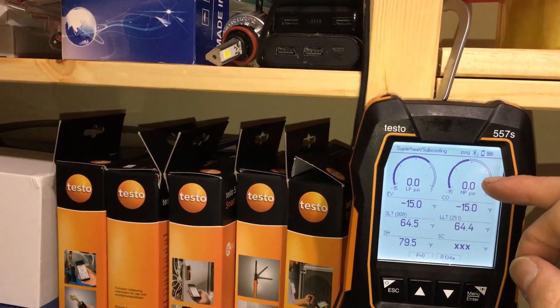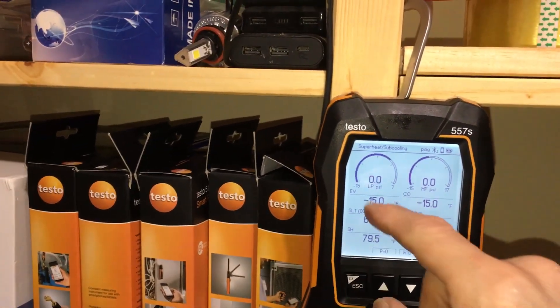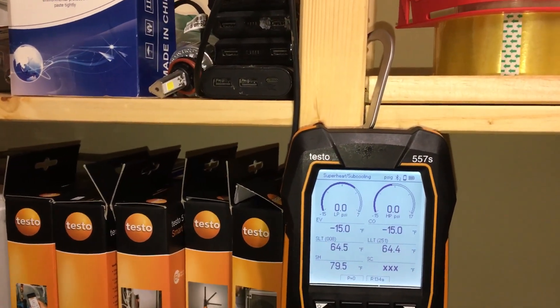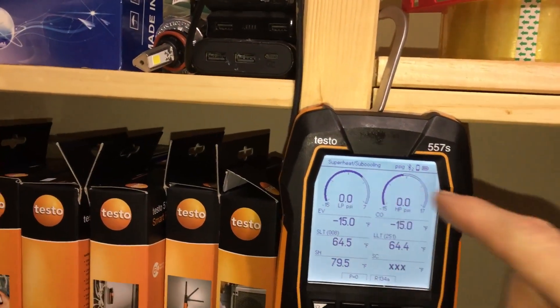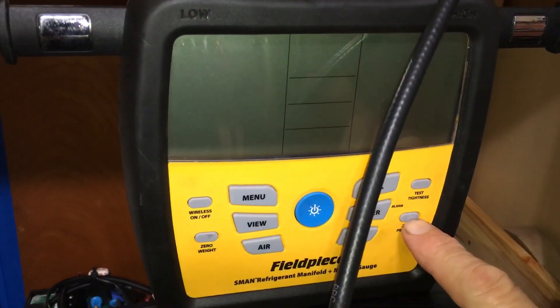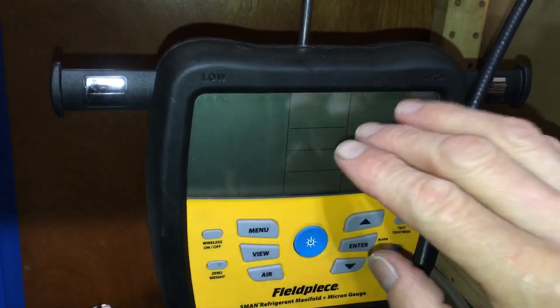So what we have here is I'm at 0-0 now, but that's not what I had. I had 8 PSI and I had like 1.5 PSI on the other side. Without going into the manual, I decided to figure it out like any other manufacturer's gauge. Everybody has a calibration button. So here's the Field Piece, and right here is the zero pressure button. You press and hold that, and when you have different pressure, it'll calibrate to atmosphere.